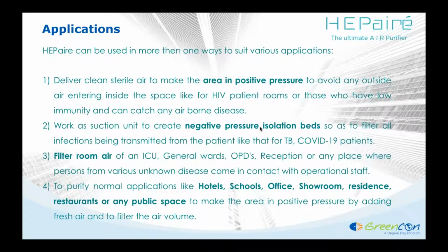I would not say isolation room. I'm taking a step ahead and talking of isolation bed. It can filter the room for a normal application like an ICU or general ward. I've even had cases where a regular operation theater, where they don't have any other option, put that in, and they've done a third-party test to see that it was actually classifying for an ISO Class 5 kind of scenario. I have test results, I'll show that to you.